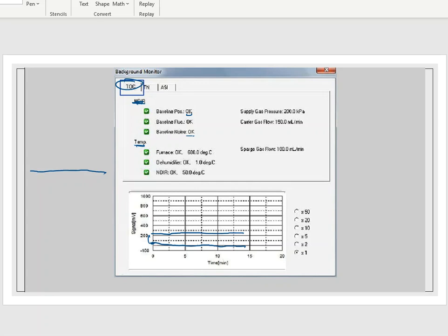So the signal limit here is 200 for our Shimadzu. If it's lower than 200 in signal, which is millivolts, then that machine will be okay. It will not like the elevated baseline, but it's okay with it. And it will let you run samples, and you can still get data, and you can still record.